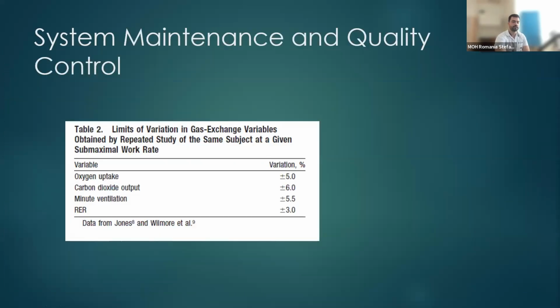In terms of the maintenance and quality control of the measurements that you are doing with the cardiopulmonary exercise testing, I'd say that it's important that the validation of the CPET system be performed on a regular basis. The gas exchange measurements are highly reproducible within a given subject if testing methods are consistent. One method that is also described in the official position papers of the American Heart Association and also the European Association of Preventive Cardiology is to validate the system's performance with test laboratory staff members at submaximal to maximal work rate on a periodic basis. The recommendation is to do this every 4 to 6 months.